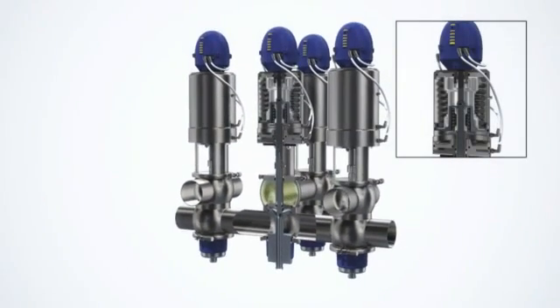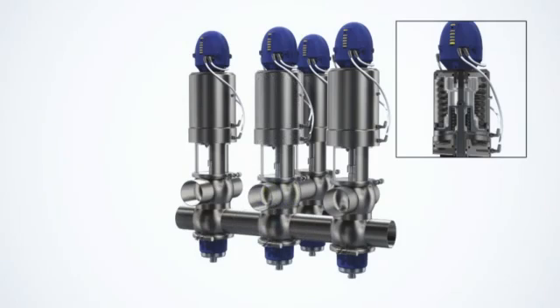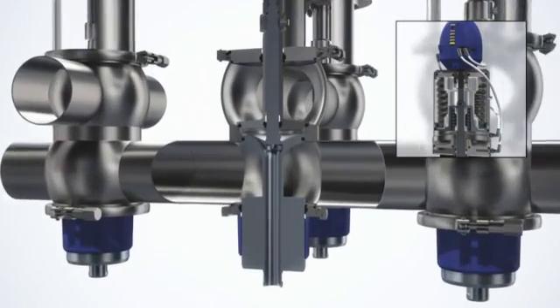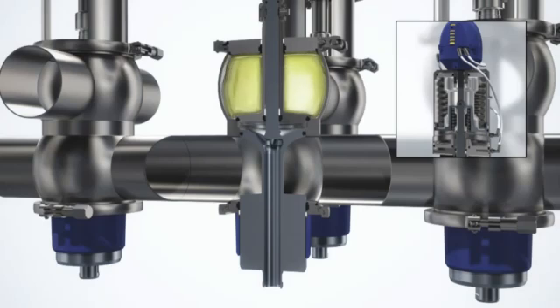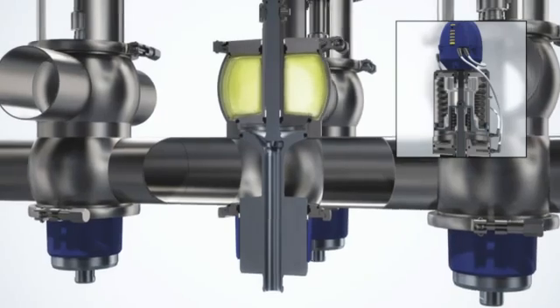If necessary, multiple seat lift operations can be performed. With a unique mix-proof valve, you get double block and bleed functionality in one compact valve. In the event of plug seal failure, leakage will be visible at the bottom of the valve.